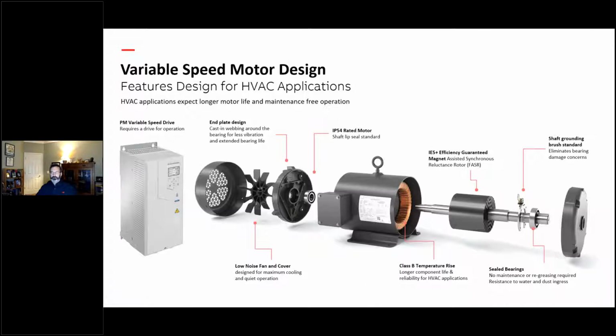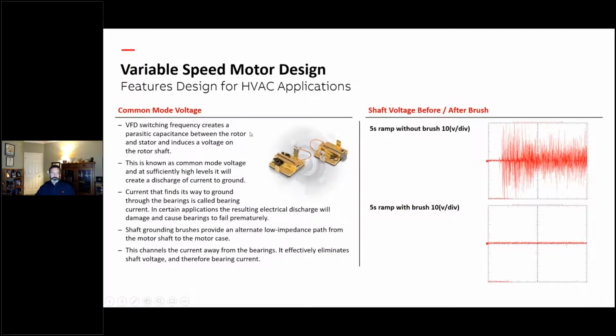Now, if you're on a floating shaft fan blade, that's not a big deal because it's going to find the shortest path to ground, and that's going to be through the motor frame. But if you're on a pump or something, you've got to ask yourself, where did that voltage and that current go? And this is what it looks like. So the VFD switching frequency creates parasitic capacitance between the rotor and stator, and that capacitance induces a voltage. And this is that voltage you see here.